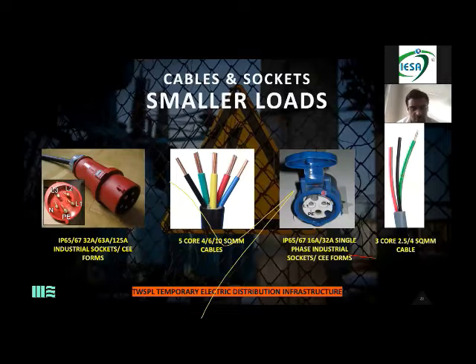Again, when you are distributing single phase, which is required mostly for your event plug points, where you have 500 plug points, 200 plug points, as soon as you start using these kind of sockets for your plug points, this earthing wire will go through and through. Whatever the size of the venue, 1000 meters, wherever the power is coming from, the earthing reaches the end point of the plug point also. Normally, what I have seen, whenever the plug points are being distributed, there are only 2 color wires, one black and one red. I think most of you must have also seen those plastic white color boxes with a switch which everybody is using. Absolutely unsafe. Absolutely unsafe. We're going to talk about why they are unsafe. That third wire, nobody wants to invest in, because again, that is for safety.